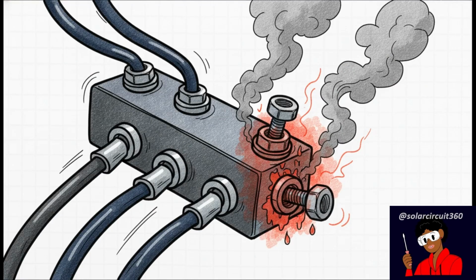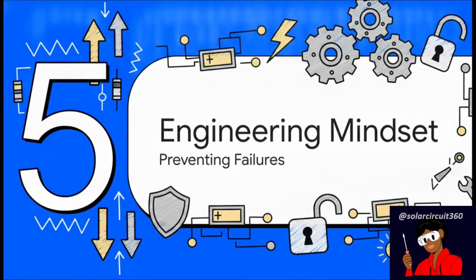Then we have bus bars. They make an installation look super clean, right? But they have strict continuous current limits too. If you expand your battery bank over time and add more batteries without checking your original bus bar ratings, you can easily turn that solid piece of metal into your weakest link. And don't even get me started on loose connections. If you don't use a torque wrench to tighten your lugs to the manufacturer's exact specs, all that resistance concentrates right at the terminal. The cable might be fine, but that loose connection becomes an intense hotspot that can literally melt your equipment.